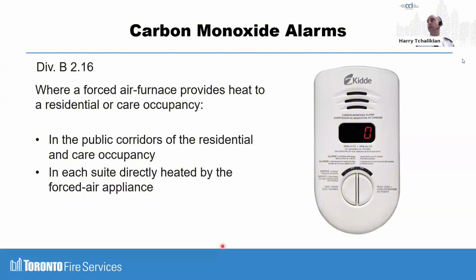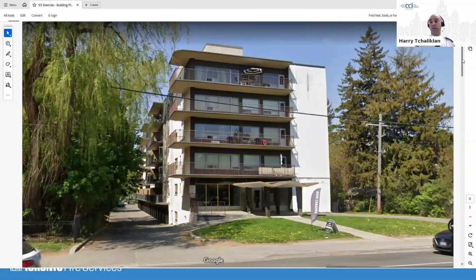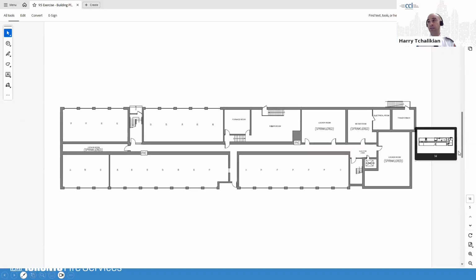Okay, so this is from an actual inspection that I had. So here's an example of a low-rise residential building. Where would we need carbon monoxide alarms? So let's look at some potential circumstances here, starting with the lowest level. And so let's see what we have on the lowest level. We have locker rooms, meter rooms, electrical rooms. So far, no. Sprinkler room, no. Here we go, boiler room. So that is implied to be a fuel-fired appliance.